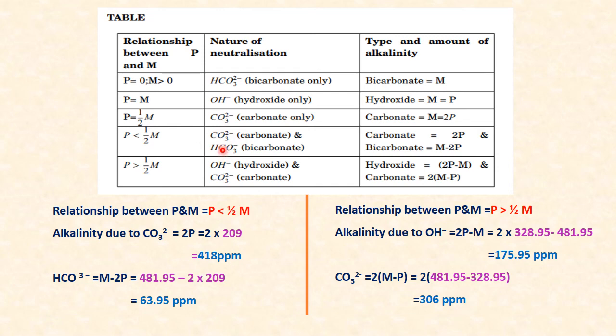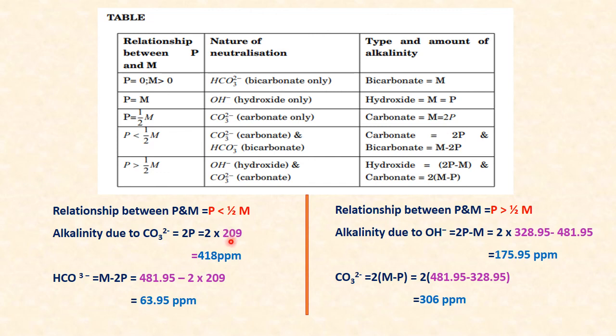If P < M/2, the ions causing alkalinity are carbonate and bicarbonate. Carbonate alkalinity = 2 × P = 2 × 209 = 418 mg/L. Since methyl orange alkalinity is total alkalinity, bicarbonate alkalinity = total − carbonate = 481.95 − 418 = 63.95 ppm. This is equivalent to using the formula M − 2P.